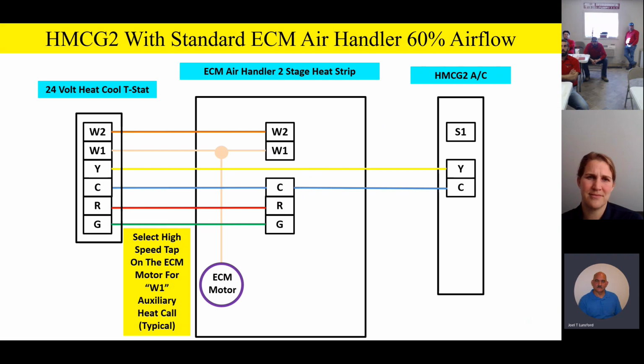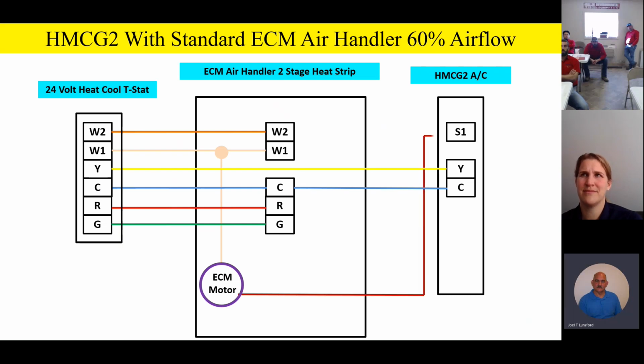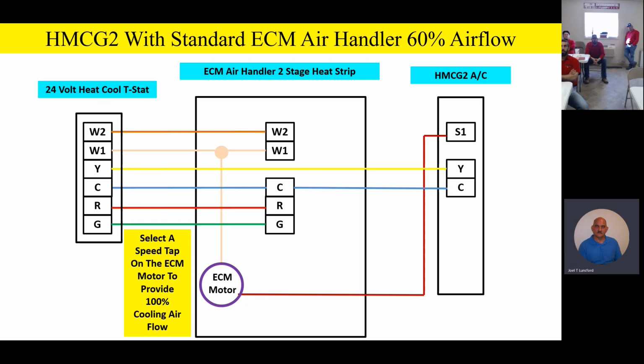Now watch this. This is exactly opposite of the heat pump. I want you cats to catch this now. On the ECM motor, we're going to select 100% airflow on S1. Now remember, on the heat pump, S1 commanded low airflow. On the straight cooling product, it commands high airflow. I want you guys to wrap your head around that. So the outdoor unit is directly affecting the speed of the indoor blower motor without a relay. S1 on the outdoor unit, the straight cooling product, is exactly opposite of the heat pump. Well, Joel, why'd they do that? I don't know. That's just how they did it. S1 commands 100% airflow.